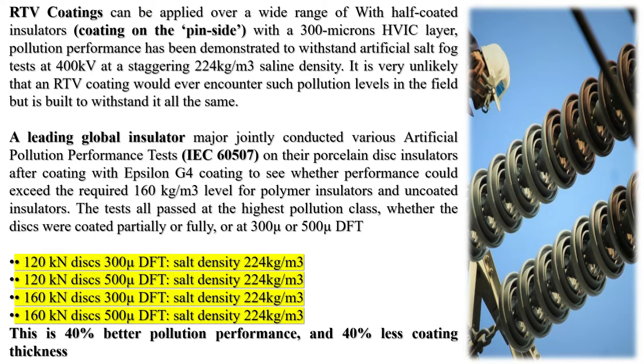RTV coatings can be applied over a wide range of configurations, including half-coated insulators with a 300-micron HVIC layer on the pin side. Pollution performance has been demonstrated to withstand artificial salt fog tests at 400 kV at a staggering 224 kg/m³ saline density. It is very unlikely that an RTV coating would ever encounter such pollution levels in the field, but it is built to withstand it all the same. A leading global insulator major jointly conducted various artificial pollution performance tests (IEC 60507) on their porcelain disc insulators after coating with G4, to see whether performance could exceed the required 160 kg/m³ level for polymer insulators and uncoated insulators. The tests all passed at the highest pollution class, whether the discs were coated partially or fully, or at 300μm or 500μm DFT — this is 40% better pollution performance and 40% less coating thickness.